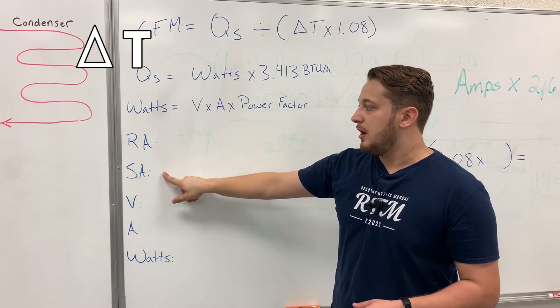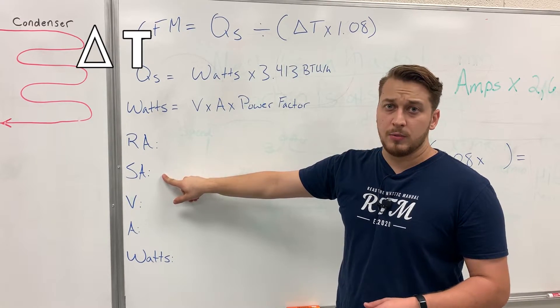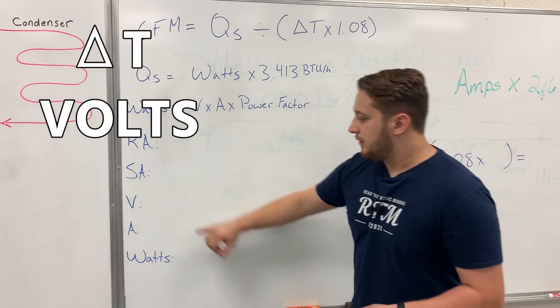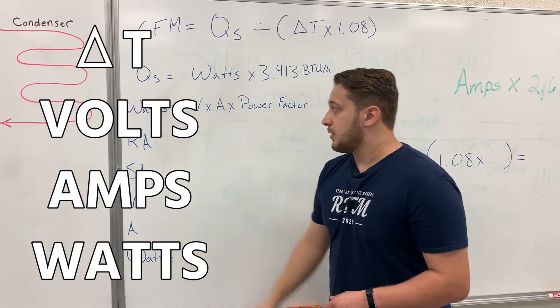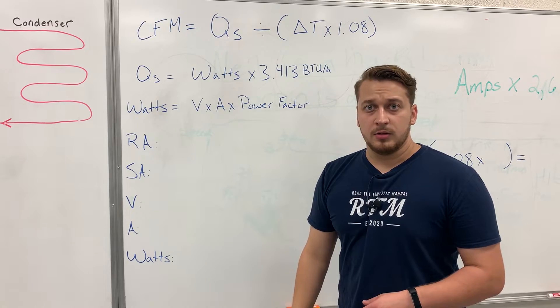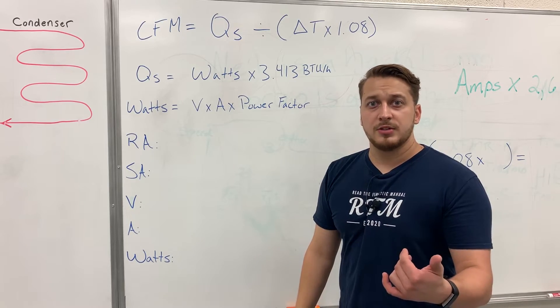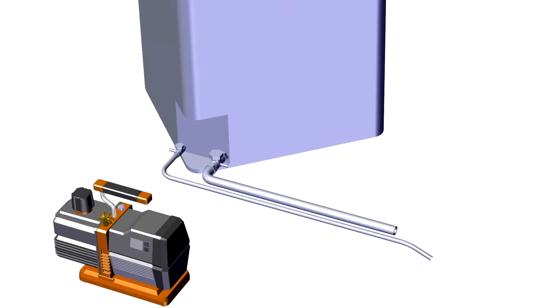We're going to get our delta T from the difference between our return and supply temperatures, and then take our volts and amps to calculate watts. We'll be working on a Goodman air handler — we're going to run the heat strips and do our calculation.